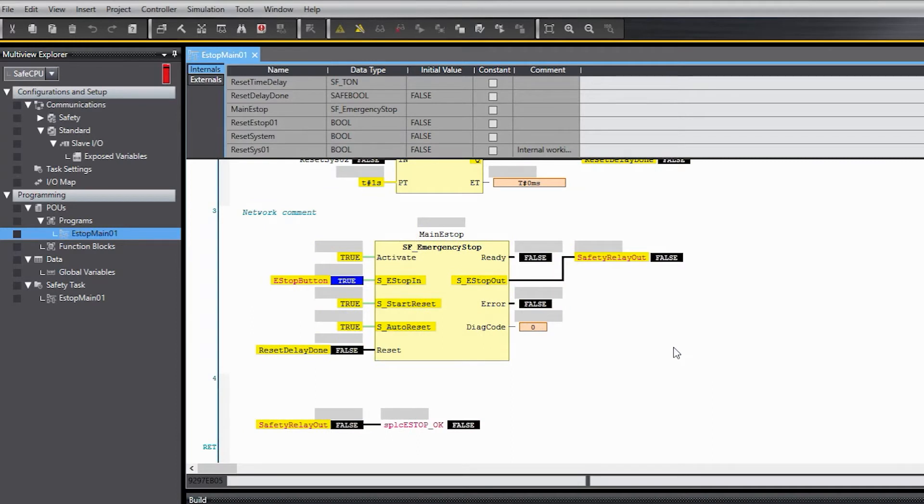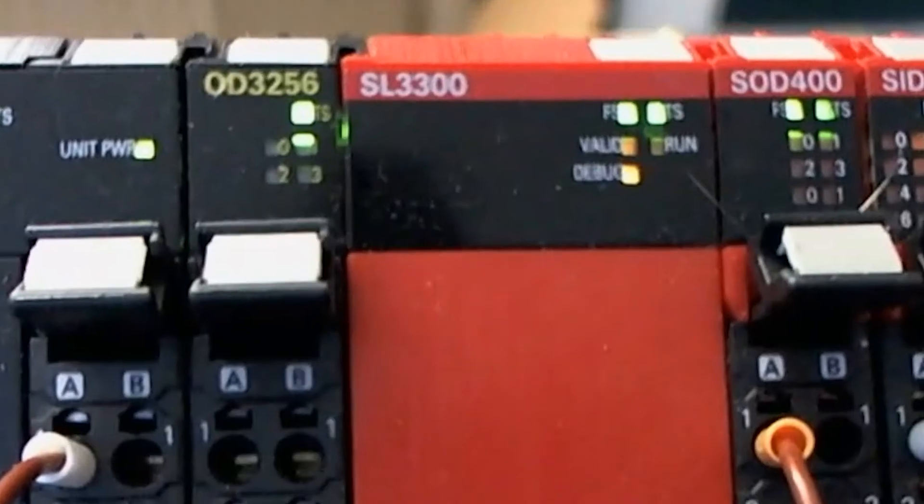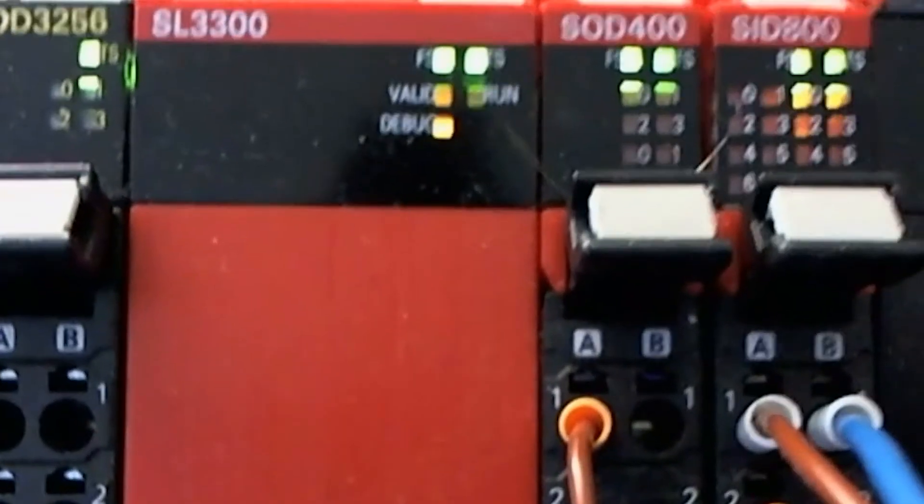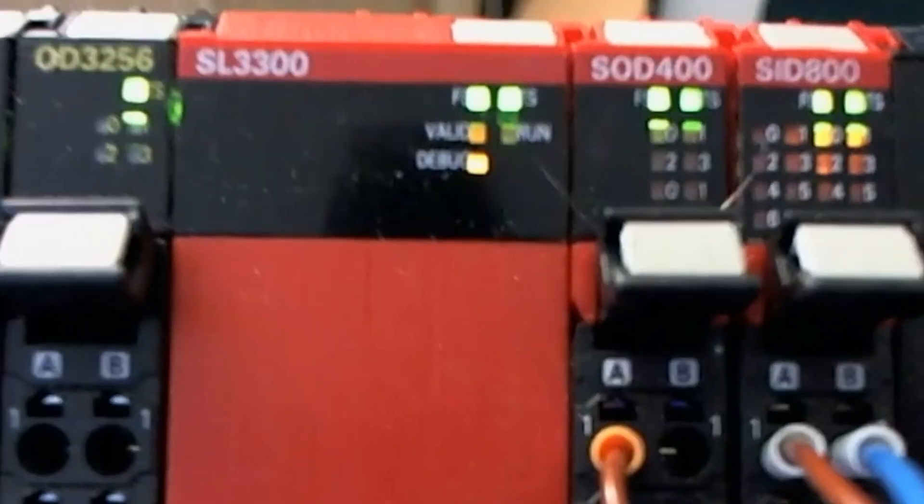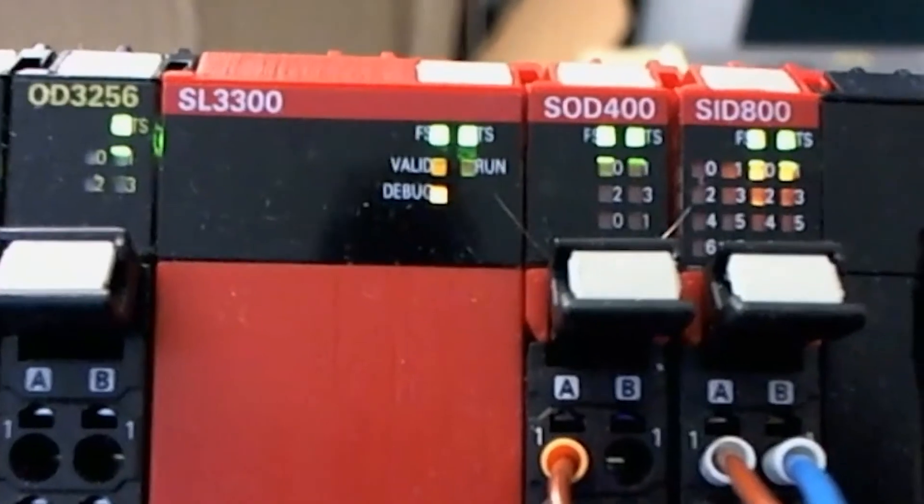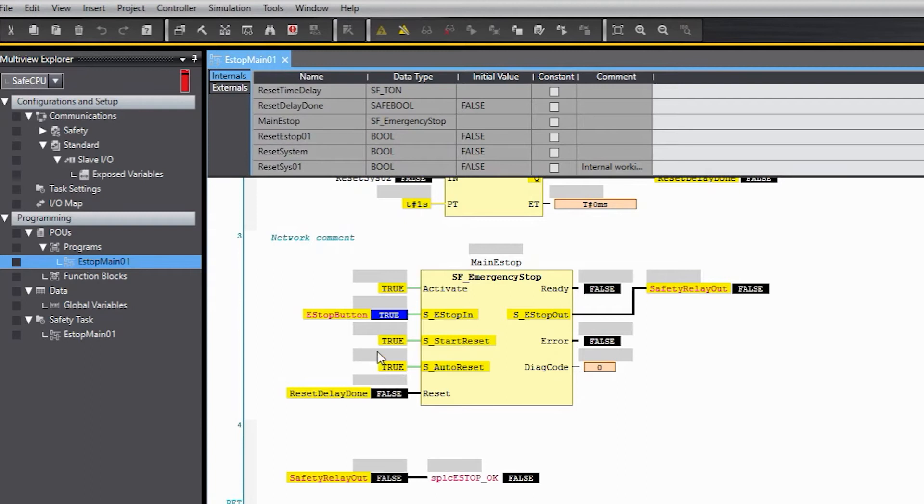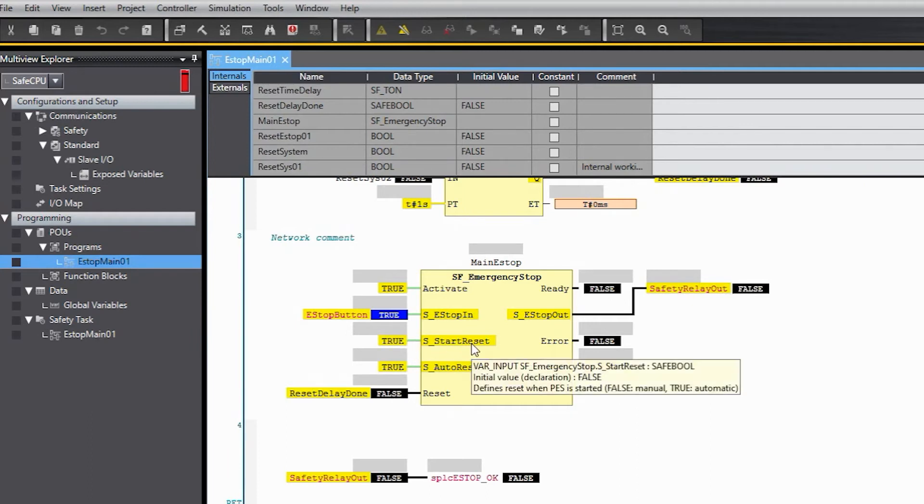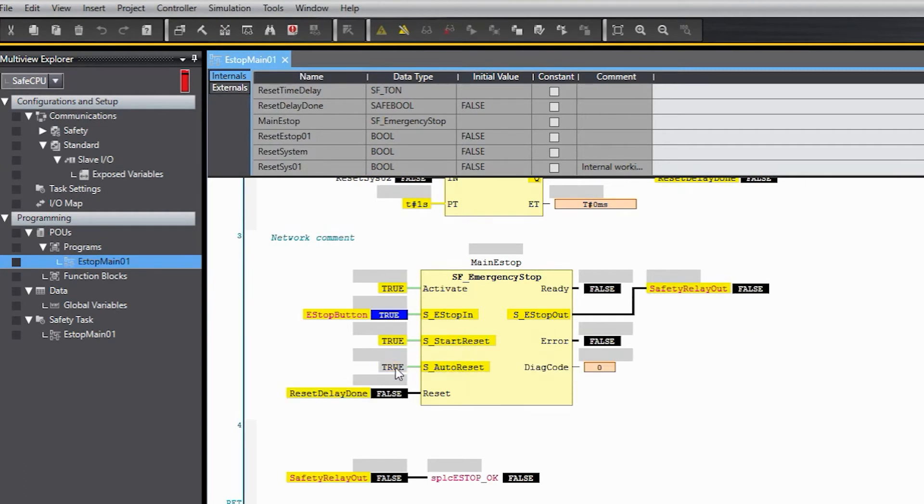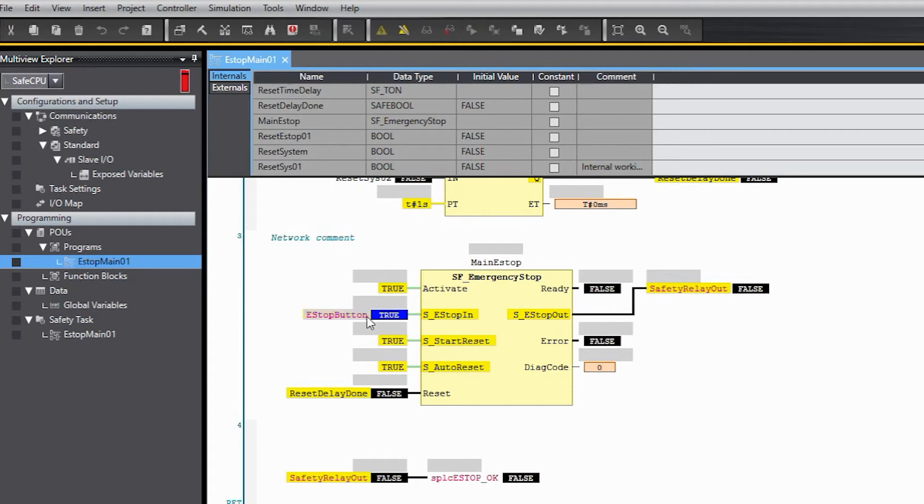Okay, so now I'm in debug mode and here you can see the LEDs on the controller. The debug light is on solid, the lights have stopped flashing, and the run light is off. And you can see based on these two inputs being true that if the safety CPU is running then this output should be on because this one means that it's going to automatically reset the output, meaning turn it on when the PLC first powers up. And then this one means it's going to reset whenever those input conditions are satisfied as they are here where the safety e-stop is true.